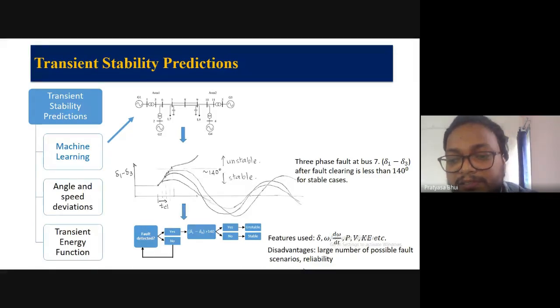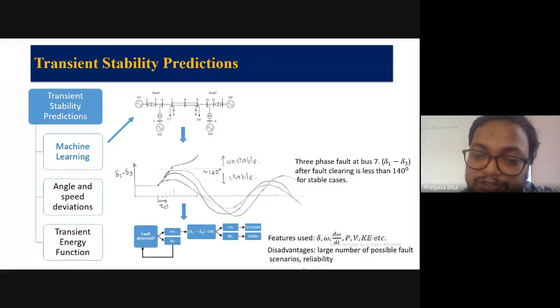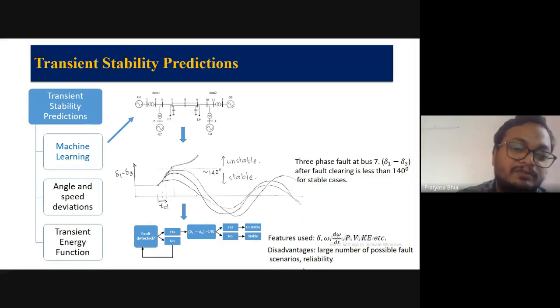But the disadvantage is that because of the large number of possible fault scenarios, it may not be reliable, because the operating condition is also changing. You might be training the decision tree for one particular operating condition, and then that operating condition changes, and then a fault occurs. So your past training data may not be reliable. Typically the features used for taking the decision are generator rotor angle, speed, acceleration, active power, voltage, kinetic energy. So many things people have suggested to use in a decision tree, SVM or support vector machine, or artificial neural network.